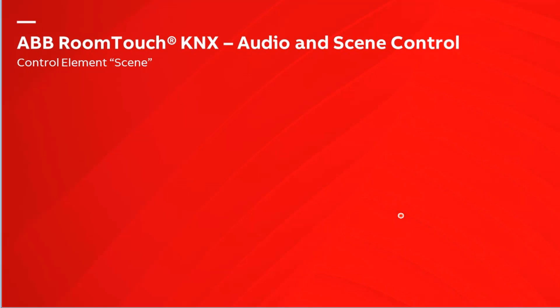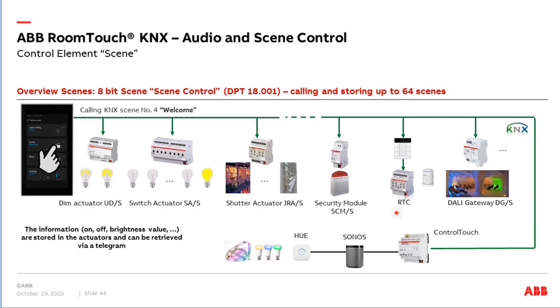Now let's come to the next topic: scenes. With the scene function we can call or store a scene — the typical 8-bit scene according to KNX data point type 18.001. With one telegram we can call or store up to 64 scenes. The big advantage is we send only one KNX telegram, and depending on the value we call or store up to 64 different scenes. The information — on/off, brightness value, lamella position, angle, HVAC setpoint — is all stored in the actuator. We send only the command, and the device retrieves the stored values.